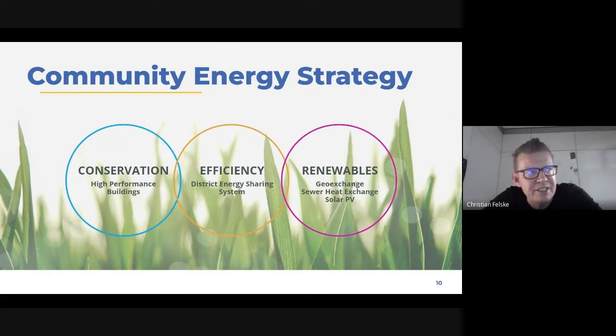The second pillar is about efficiency, and this is where an ambient district energy sharing system comes into play. It's an ambient temperature system that works with extremely efficient heat pumps in our central district energy plant, but also in the homes built in Blatchford. So these buildings, to put it simply, won't have a natural gas furnace or a natural gas hot water heater. Instead, they have 2 heat pump systems which provide space heating and cooling, as well as a heat pump for domestic hot water provision.